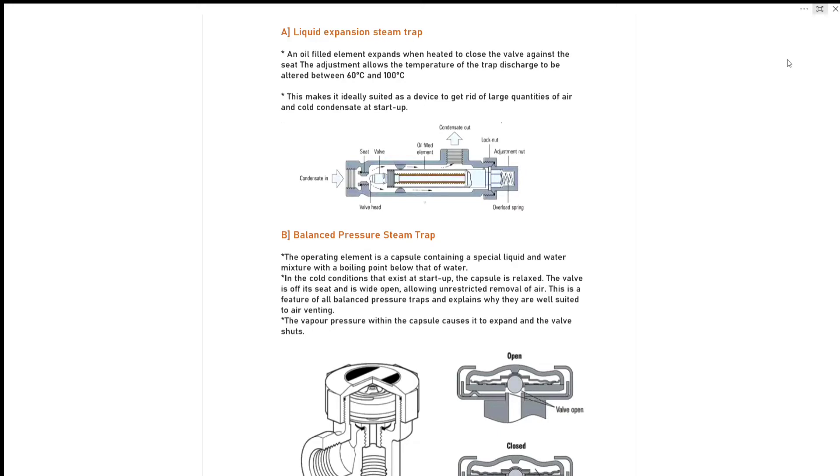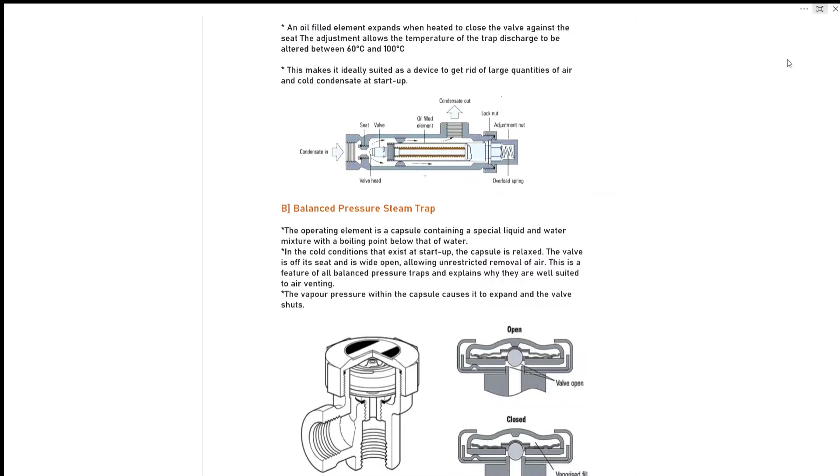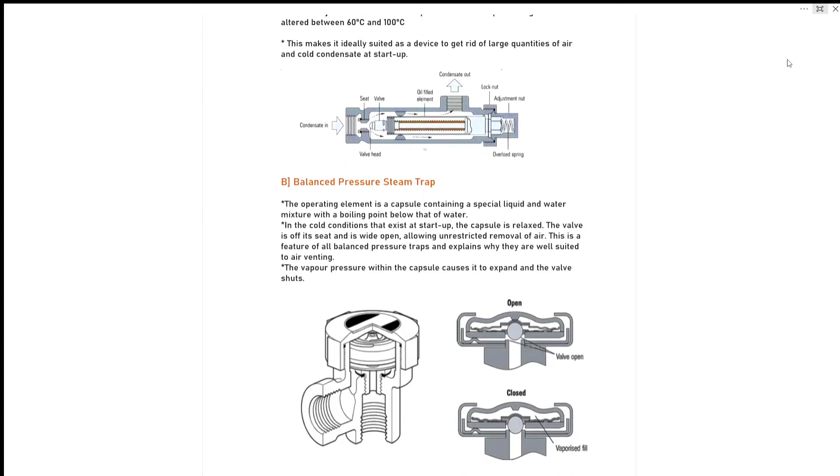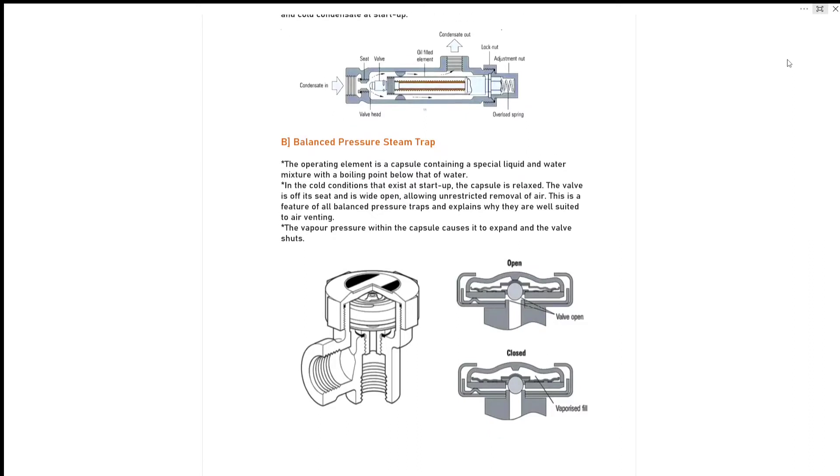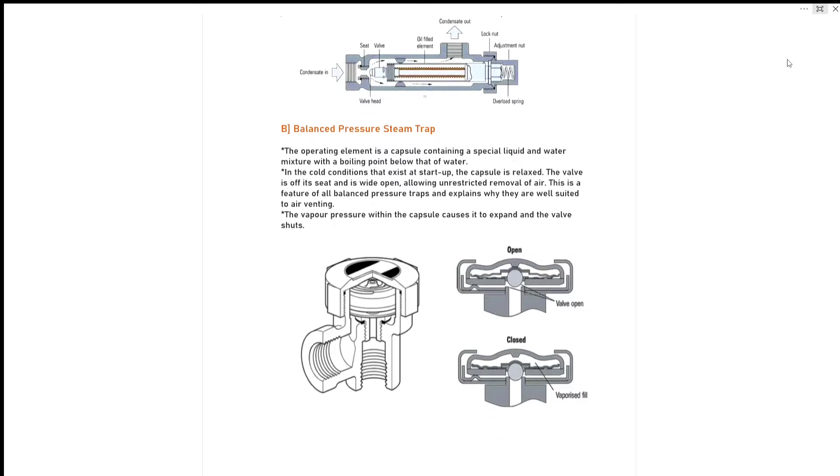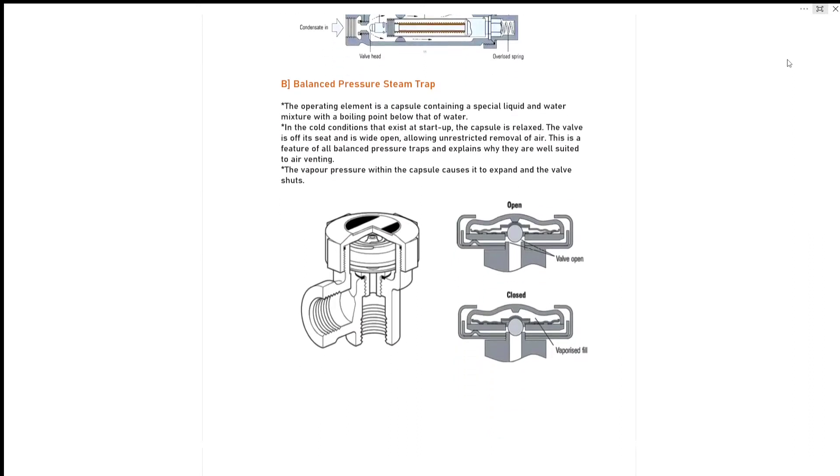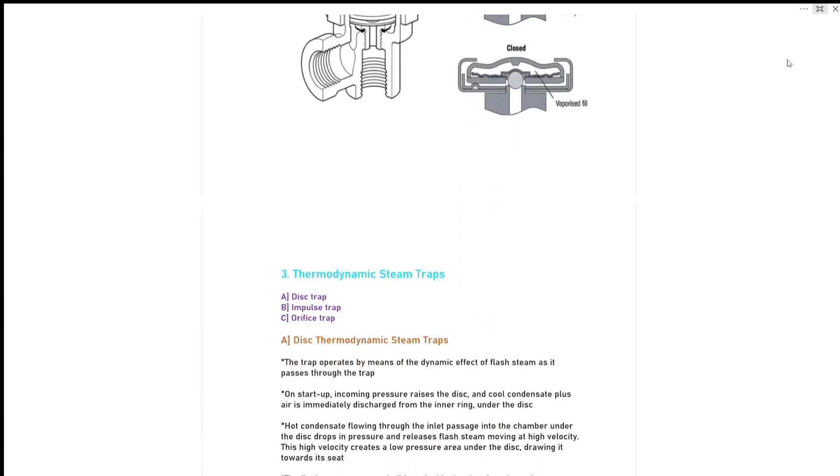Second type is balanced pressure steam trap. The operating element is a capsule containing a special liquid and water mixture with a boiling point below water. In the cold condition that exists at startup, the capsule is relaxed, the valve is off its seat and it's wide open, allowing unrestricted removal of air. This is a feature of all balanced pressure traps and explains why they are well suited to air venting. The vapor pressure within the capsule causes it to expand and valve shuts.